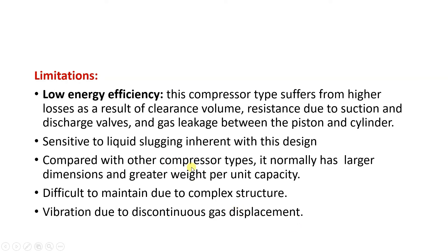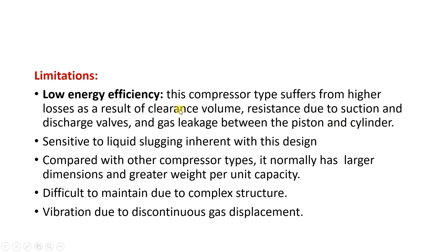What are the limitations of this reciprocating type of compressor? First one is low energy efficiency because of clearance volume. In a cylinder with walls, there is clearance volume at the top. This clearance volume is large for reciprocating compressors, causing losses. The gas that remains after discharge expands in the clearance volume, so there is a re-expansion effect on the discharge pressure, reducing efficiency.